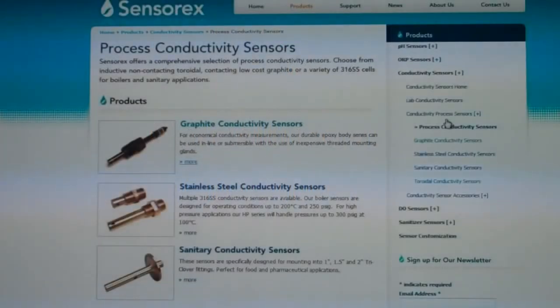Conductivity electrodes must be calibrated with the instrument the very first time you will use it to take a measurement. They should also be recalibrated when you suspect the sensor may be out of calibration, or on a periodic basis to verify that your calibration remains accurate.